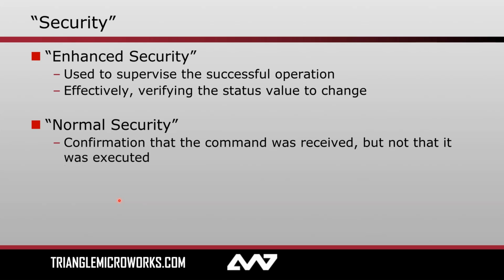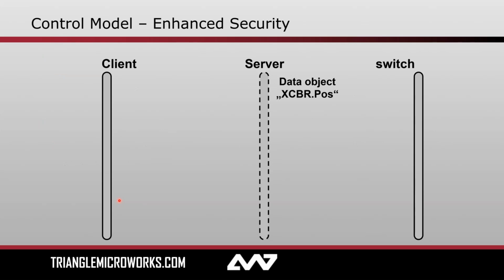So just to reiterate, enhanced versus normal security. Enhanced security is used to supervise the successful operation, if I actually want to know that my device actually did what I was hoping that it would do. Whereas normal security includes no confirmation that the control was successfully carried out, only that it was accepted and attempted. And we kind of see this in action on this next slide. Some of you might be wondering, why would I actually do normal security? Typically, you wouldn't. You're really going to use enhanced security for most operations, really just for internal or local operations, things that are lower stake. That's when you would use normal security.